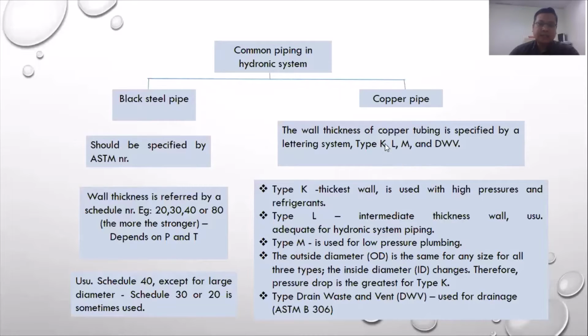So it means K is thickest, going from the higher thickness to the lower. So K is considered the highest thickness. The outside diameter is the same for any size for all three types. Inside diameter changes, therefore pressure drop is greatest for type K. So actually, the outside diameter size is considered fixed whether we select K, L, or M, but when we select from K to M, the inside diameter changes. So if the inside diameter is higher, it means the thickness is lower.